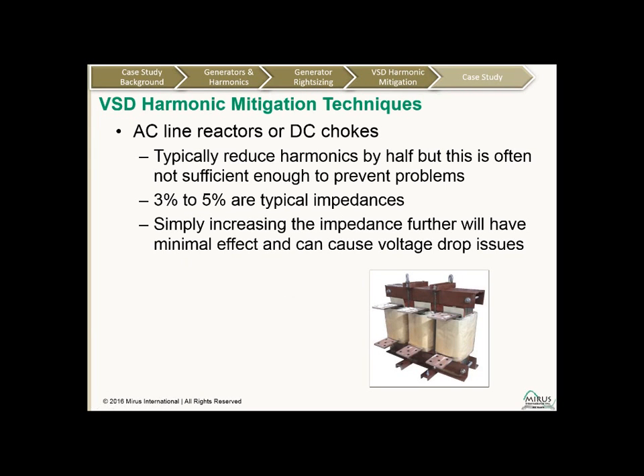So let's look at a few forms of harmonic mitigation that are available to us today. In the application that we're using for our case study, they did include an AC line reactor. So we can have AC or DC chokes that are used on drives. Typically, they'll reduce the harmonic distortion by about half. And that almost always is not sufficient to resolve the problems associated with the harmonics.